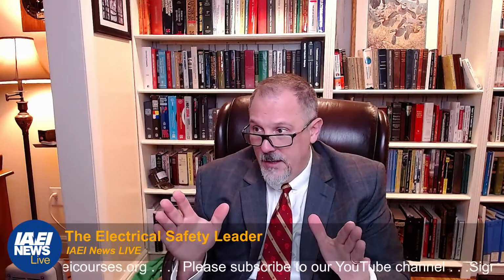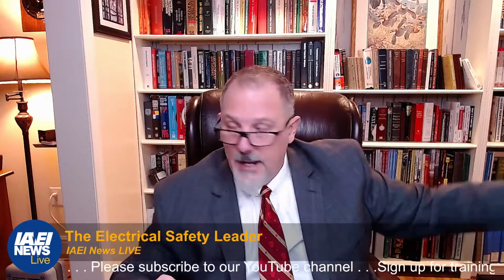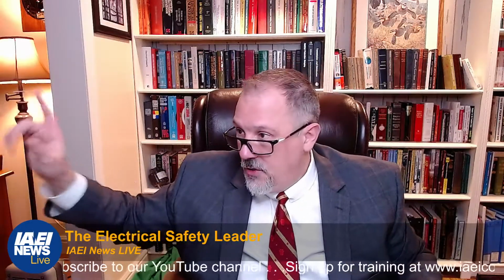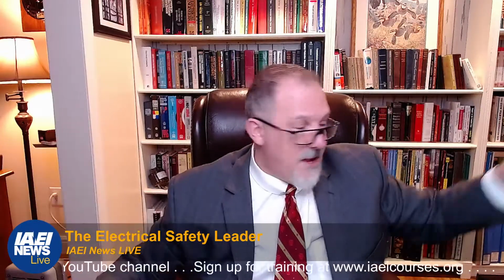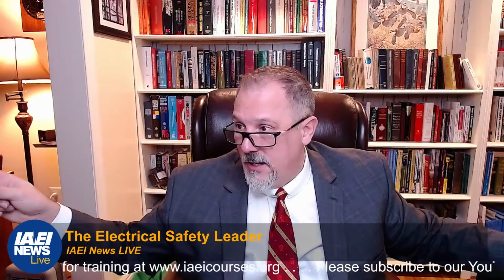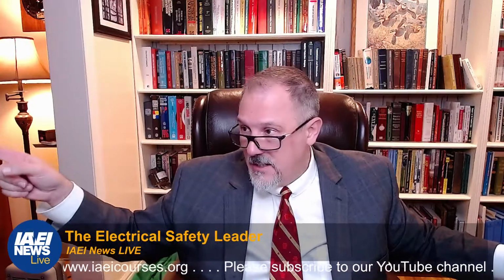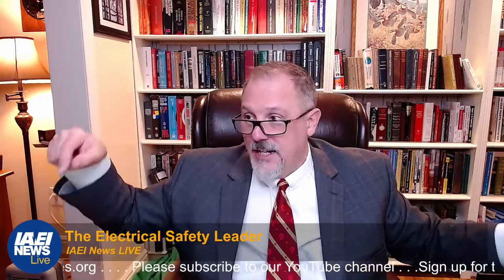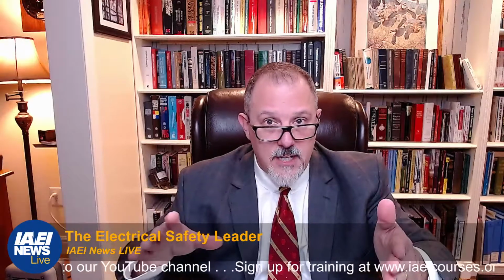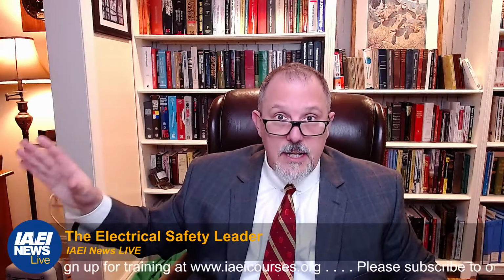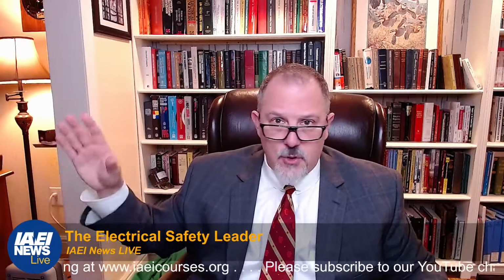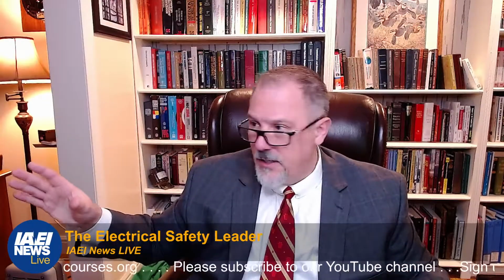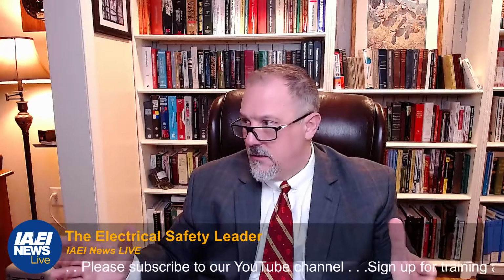All they're saying there is if I'm working on a panel board and I have a safety disconnect switch, I can use that safety disconnect switch to turn off that panel board, establish an electrically safe work condition. I can lock and tag it out and I can turn it back on again, but in that safety disconnect switch, I don't have to de-energize it from up above. I'm going to do my risk assessment there, right? What's my risk assessment? What condition is it in? Is it rated correctly? Is it installed correctly? Does the interrupting ratings or short circuit current ratings exceed the available fault current? All those things. I'm going to do my risk assessments.